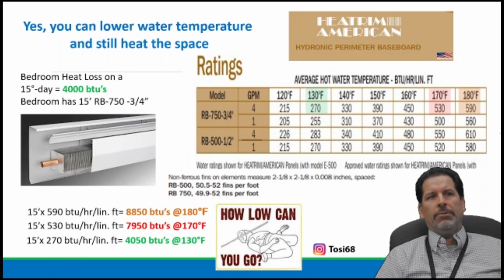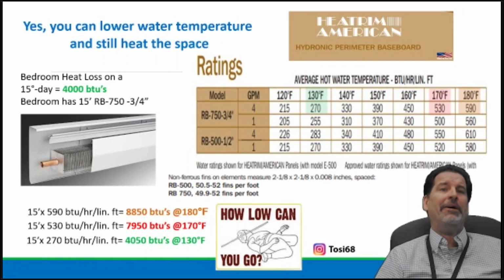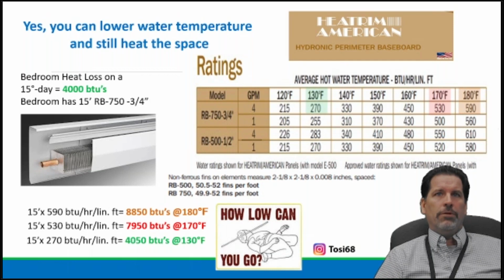Look at 130 there. We need 4,000 BTUs with 30% fudge, right? That's the calculation, the program. I went as low as 130 average water temperature, delivering now 270 BTUs for every foot of that element, and I'm now delivering just over 4,000. I am pretty spot on that that room will still be maintaining comfort at 70 degrees on a 15-degree night. That's pretty damn good. Boiler's not short cycling, right?